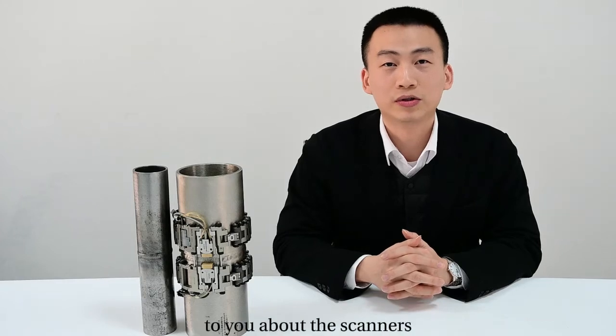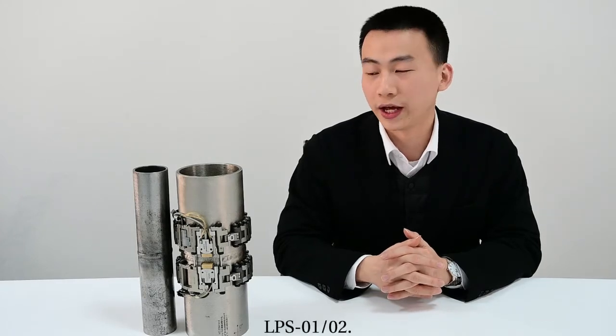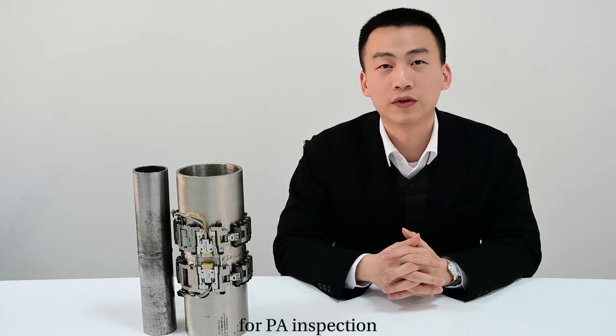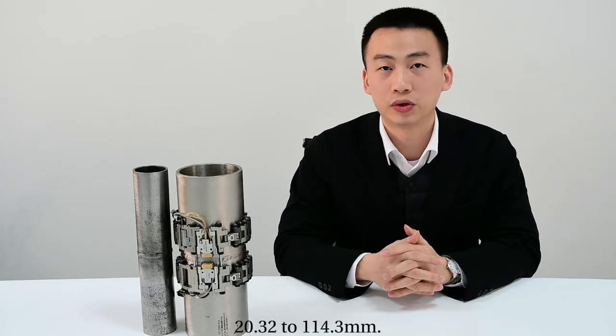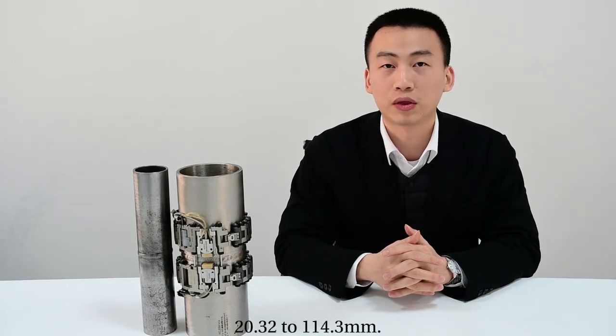Now I would like to introduce the scanners LPS-01 and LPS-02. These two scanners are suitable for phased array inspections on pipes with outside diameter from 20.32 to 114.3 millimeters.